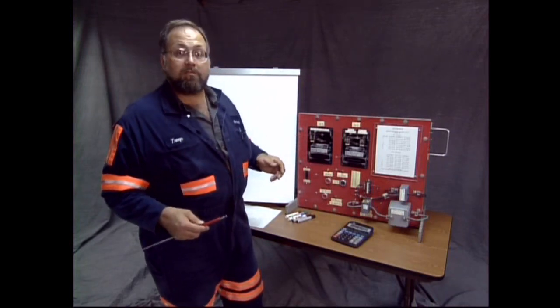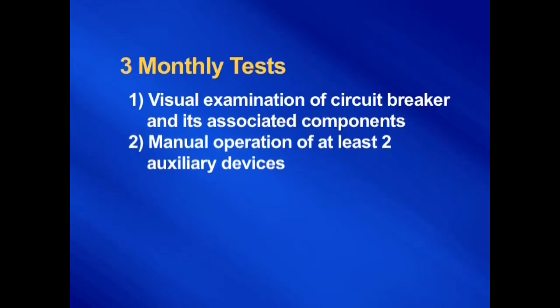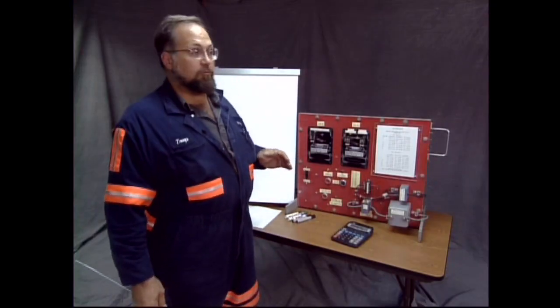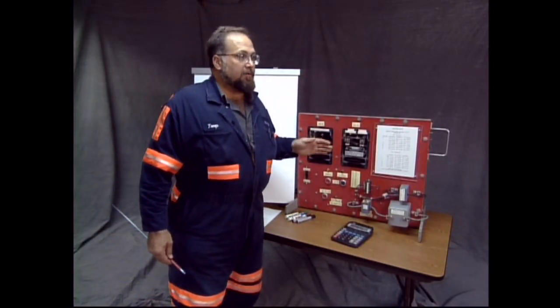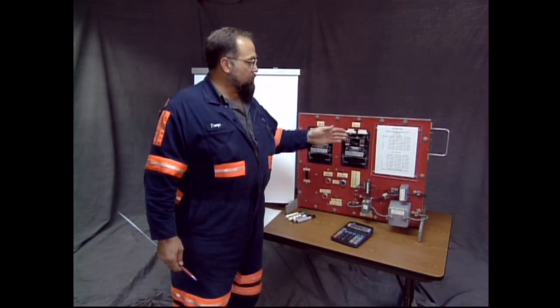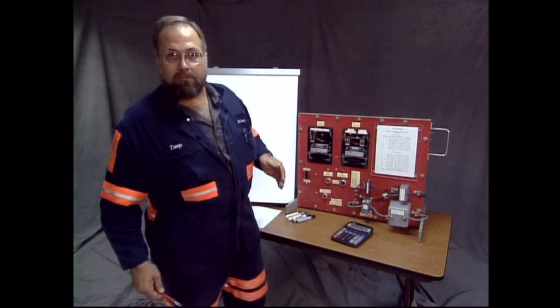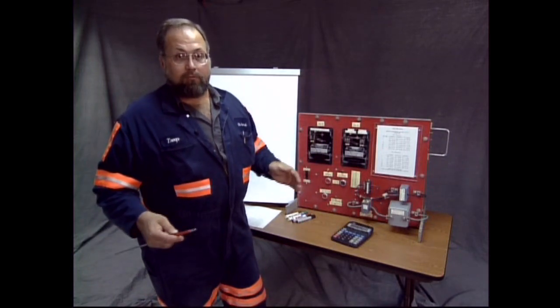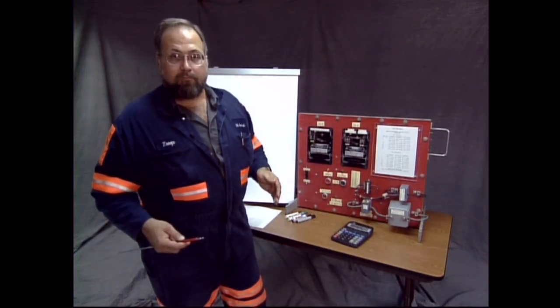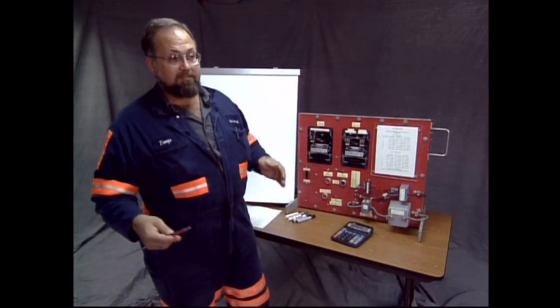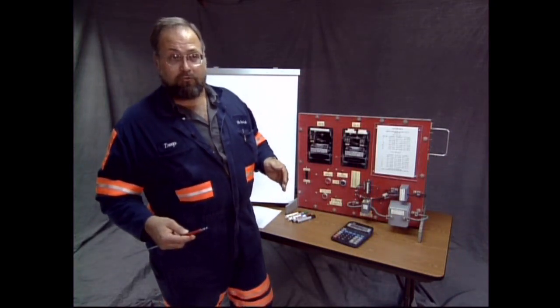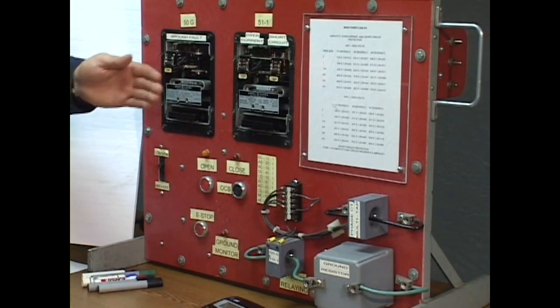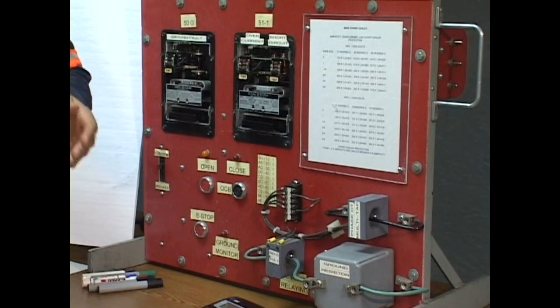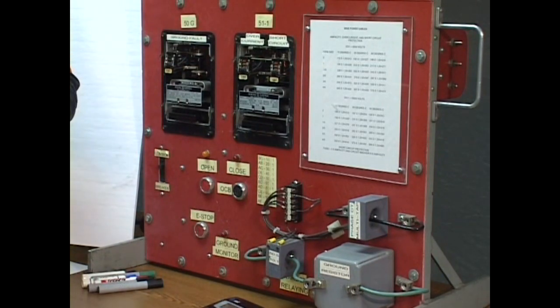Now, next, the second thing you have to do is a manual operation of at least 2 auxiliary devices. Now let's talk about this. You're going to operate this thing manually versus truly putting a fault on it. A short circuit, that would be a phase-to-phase situation. Now you don't want to be there when that happens, a real phase-to-phase. That's a catastrophic electrical event. Assets will be damaged, and some of those assets, maybe human resources assets. You don't want to do that. So you want to simulate a short circuit. You want to manually operate this relay to prove that indeed, if this relay operates, it will turn the power off.